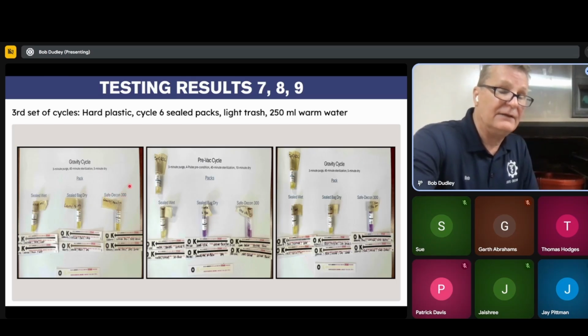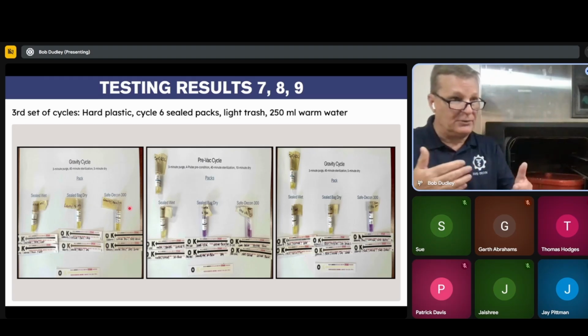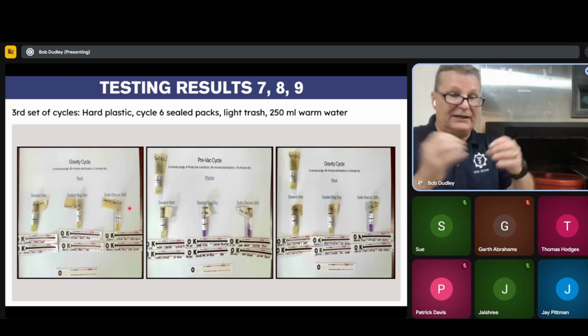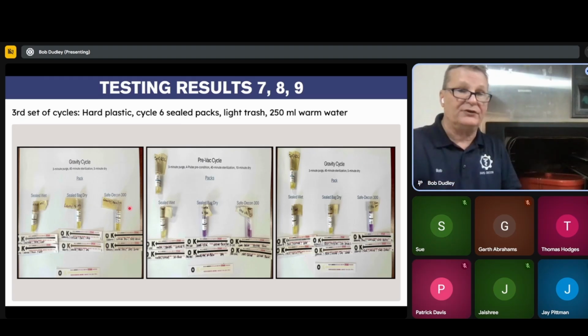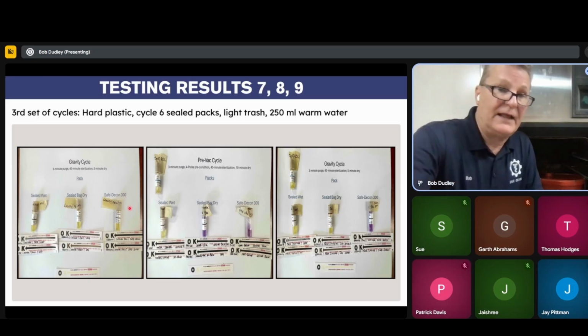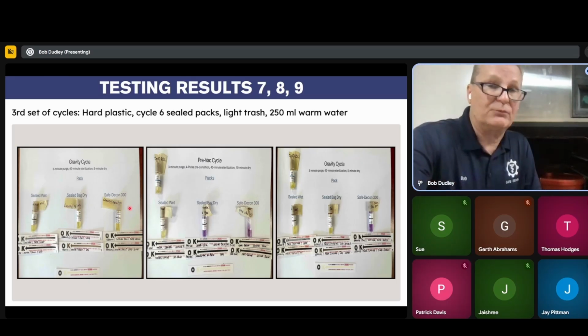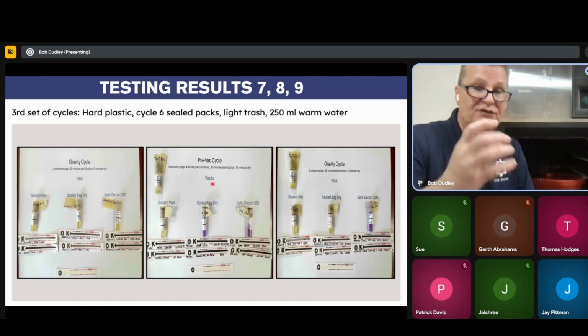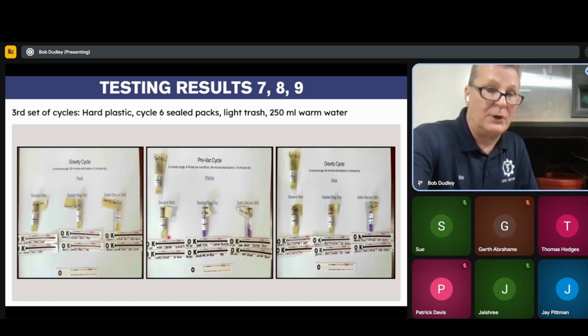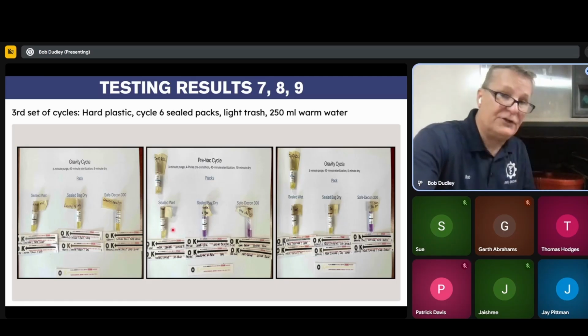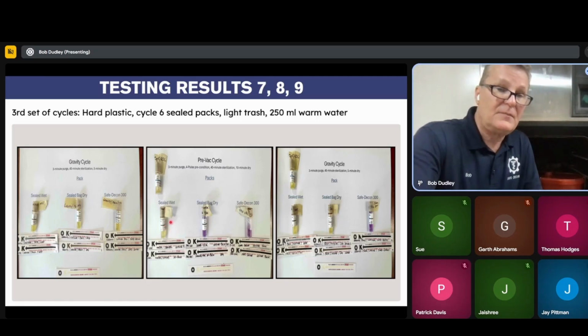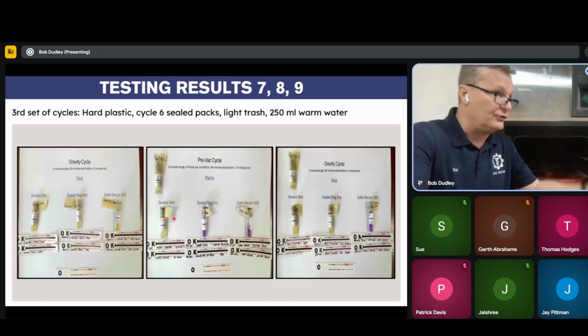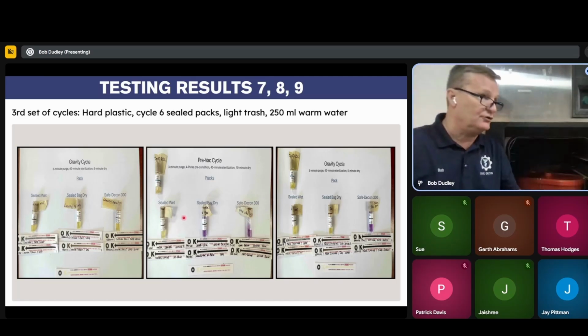And again, I figured it was going to fail here because when you have it taped down and there's a certain amount of density, it's not going to penetrate. And that's where this thing becomes a little bit tricky. So this was the last one that I ran, another pre-vac cycle. The pack was tightly packed. Both of these bags did burst, but you see, by adding water to the bag, the reason they want you to do this is because of exposure. They want you to close the bag off, add the water, and then have it go.